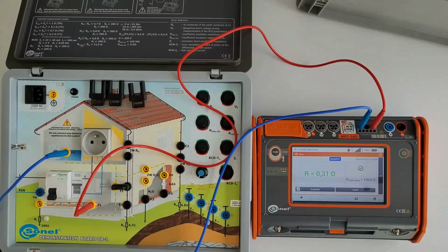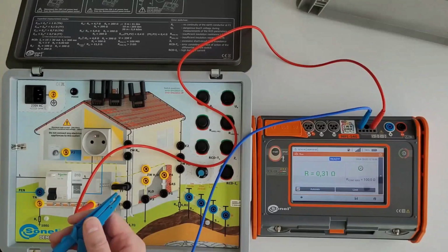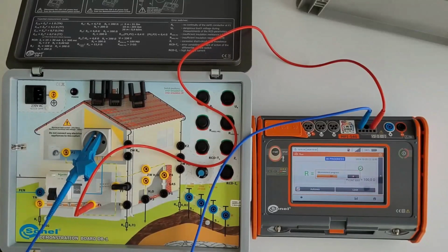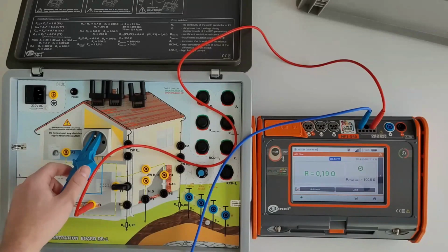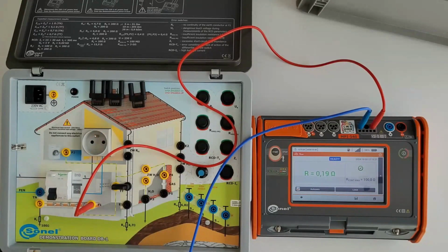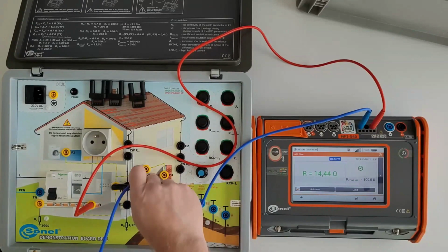We can check the continuity to the pin of the socket. We can also check continuity between the grounding bar and, for example, a water or gas pipe. In a PV system, we will check the continuity between the grounding bar and the construction and the panels. I will show you this in the next steps.